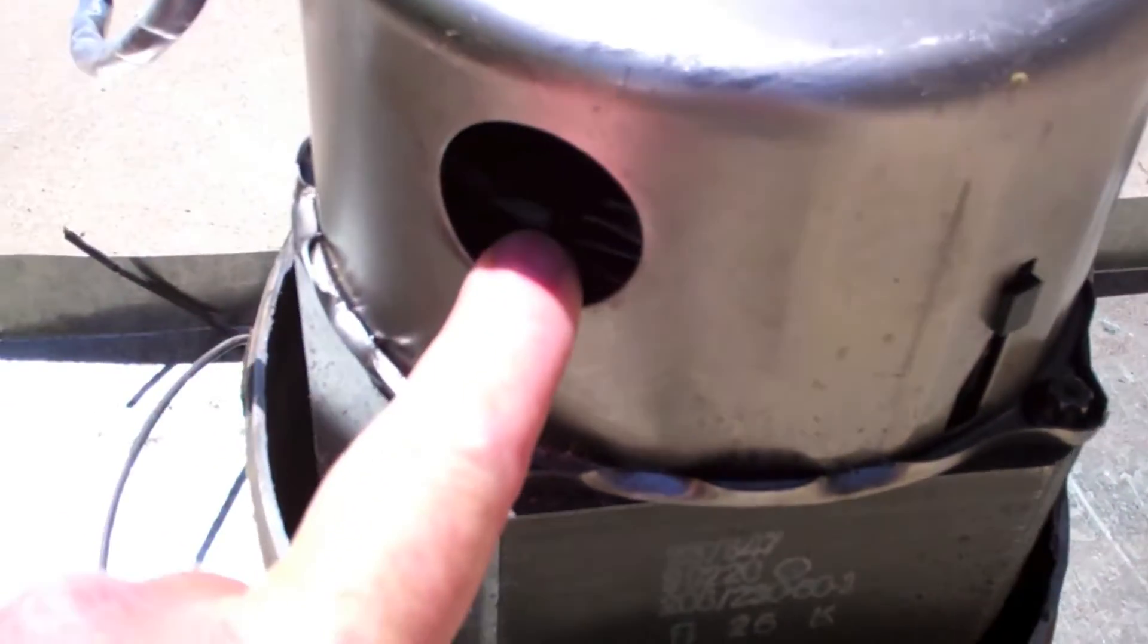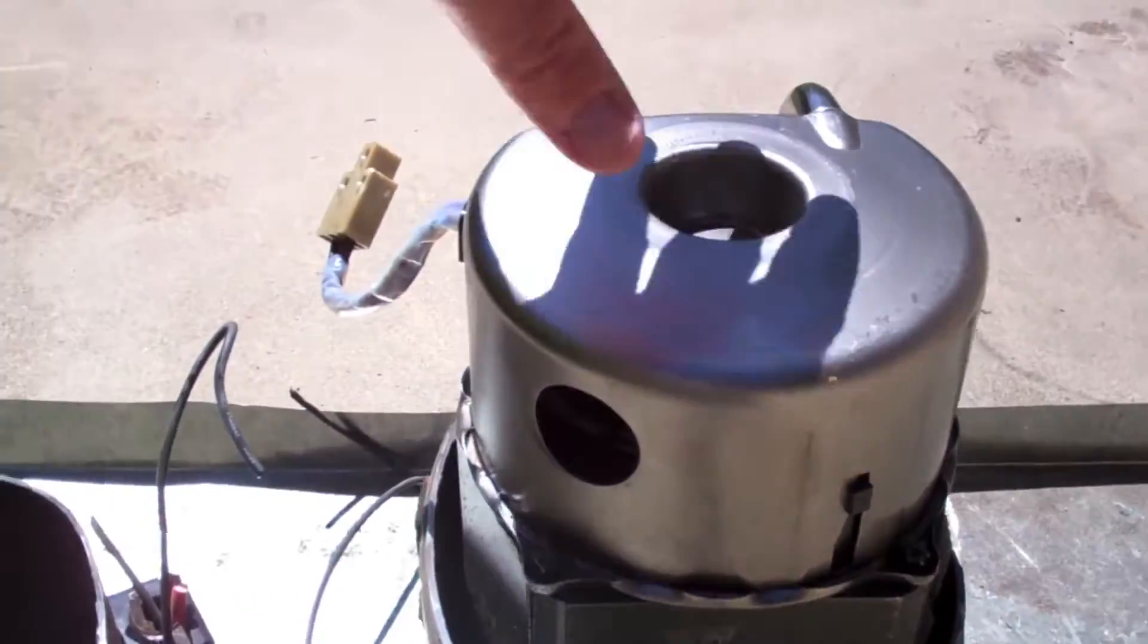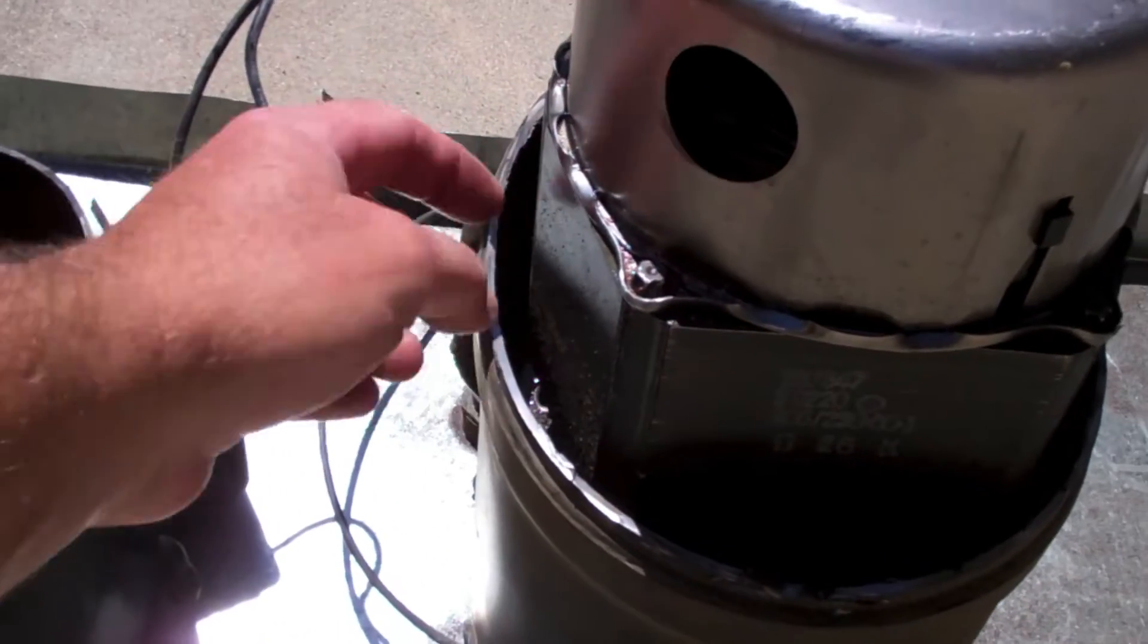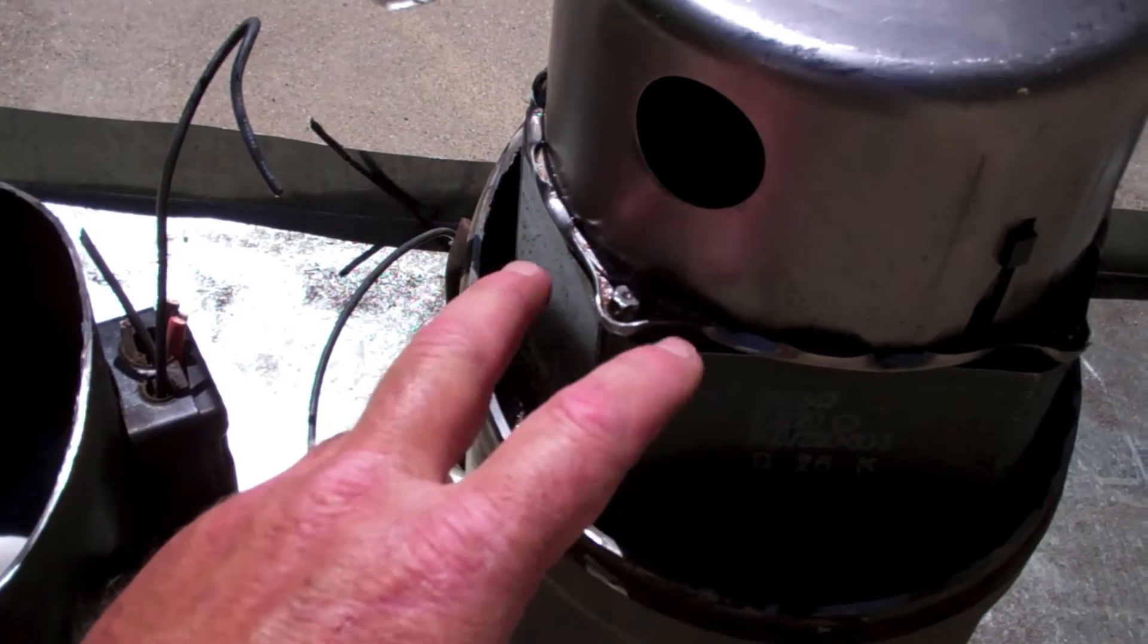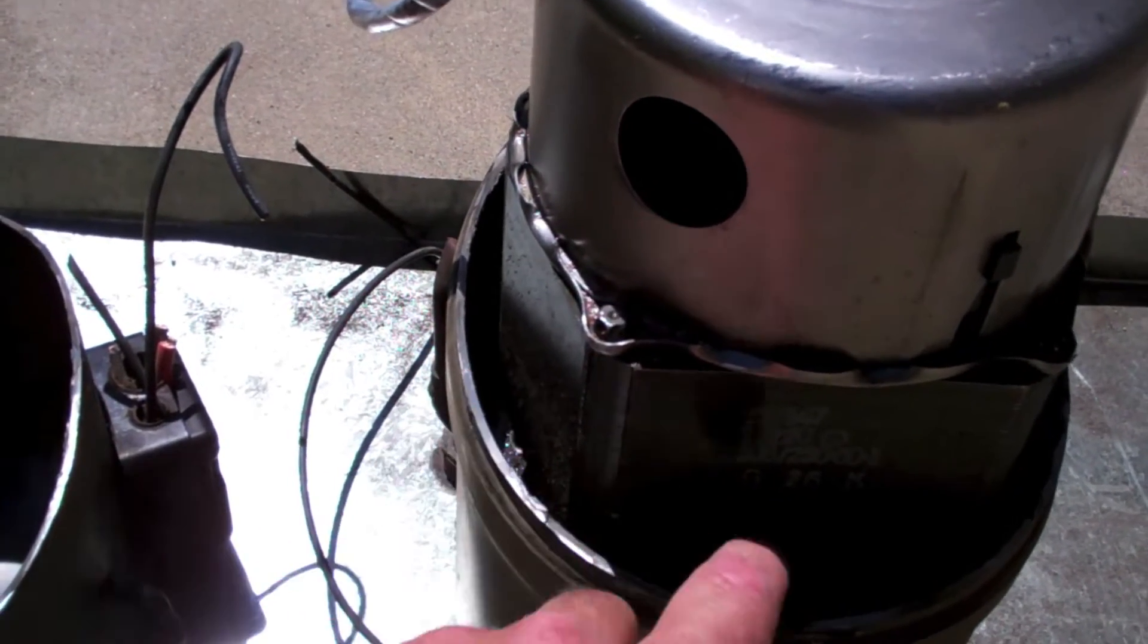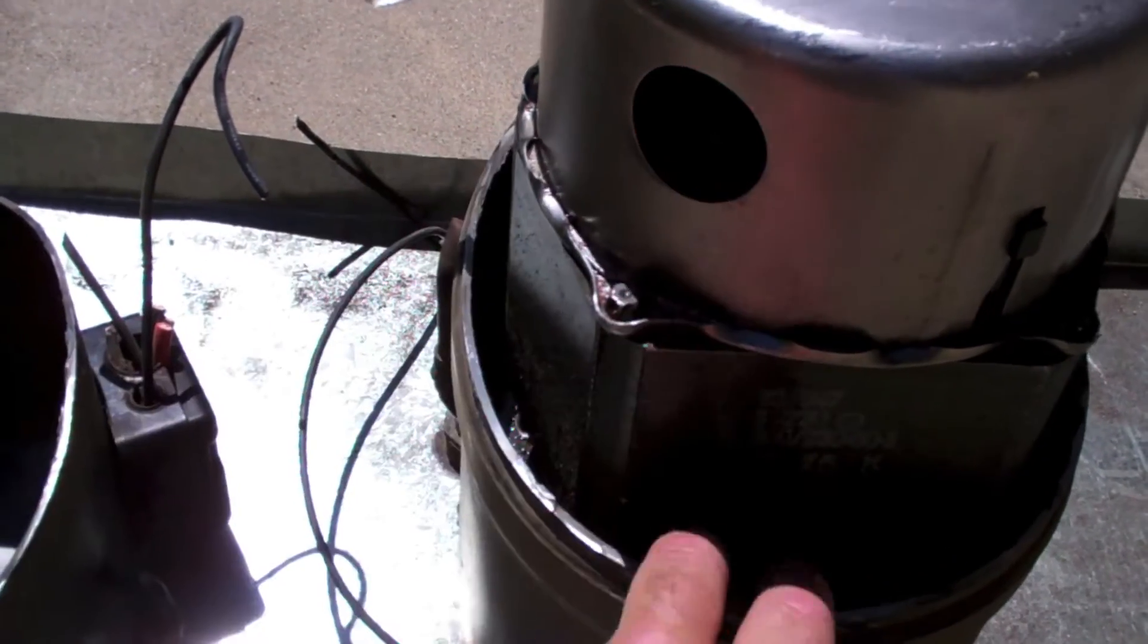But the suction gas goes in here. So this would be considered the suction side. Some of the refrigerant drops in the bottom to keep the windings cool because you've got windings here and you've got windings down at the bottom.